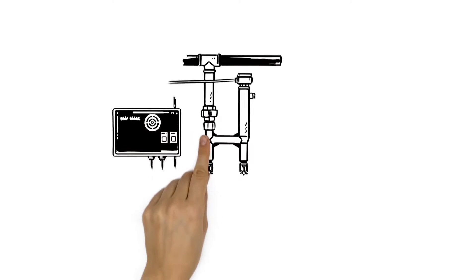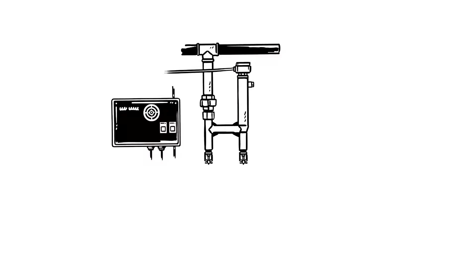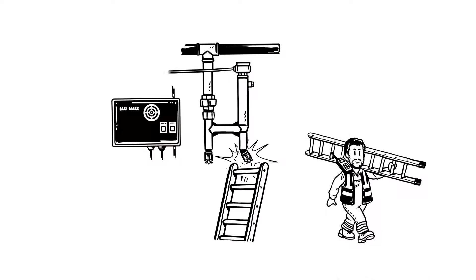It has a double-knock system, which means that if either one of its two heads is accidentally damaged, it simply sets off a warning alarm and no water is discharged.